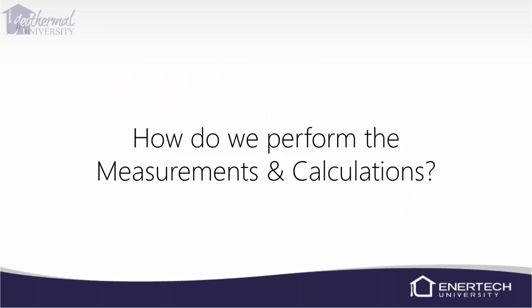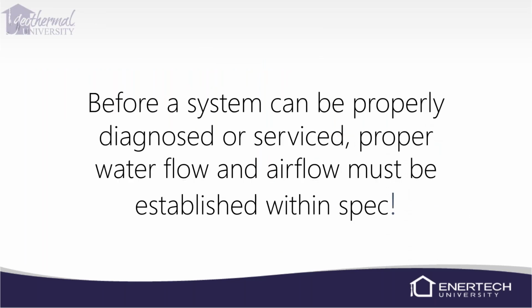So how do we perform the measurements and the calculations? Before a system can be properly diagnosed or serviced, we've got to make sure we've got proper water flow and proper airflow. Airflow, you can look at the ECM board, watch the little blinks, one blink for every 100 CFM, so you can kind of see what your airflow is. Water flow, I guess you can put your hand on a pipe and say, I can feel it moving, but that doesn't tell you that it's proper water flow. So without flow meter tools or pressure gauges, there's no way to know what our water flow is. So make sure we've got those correct tools, and we've got to establish those first.